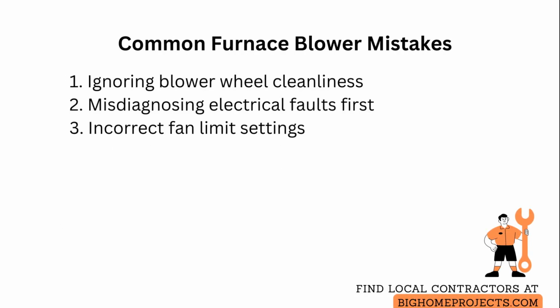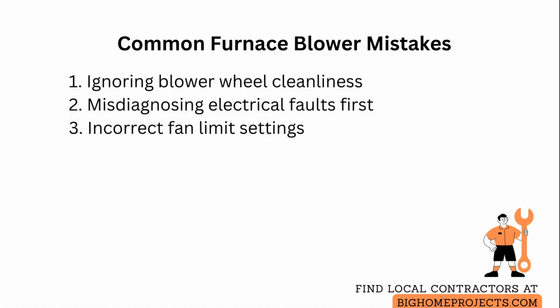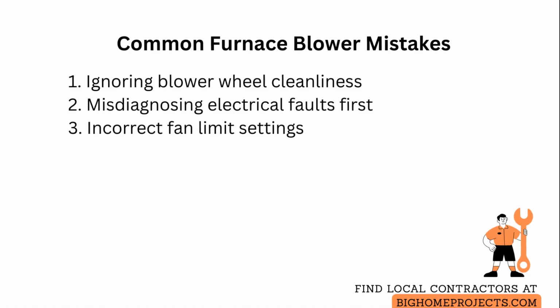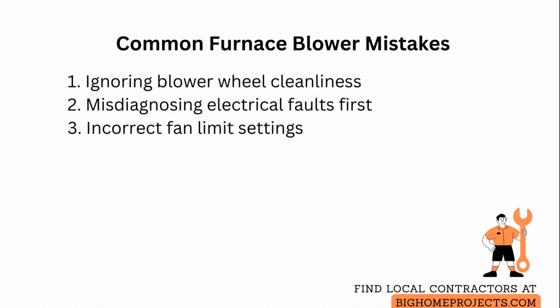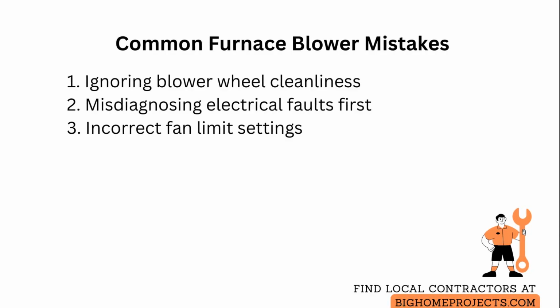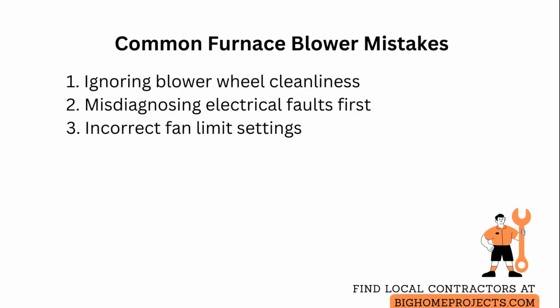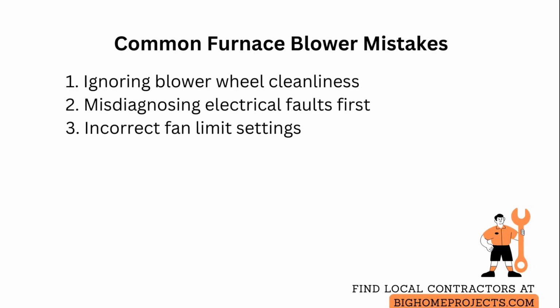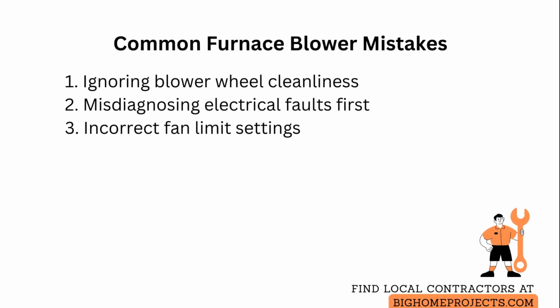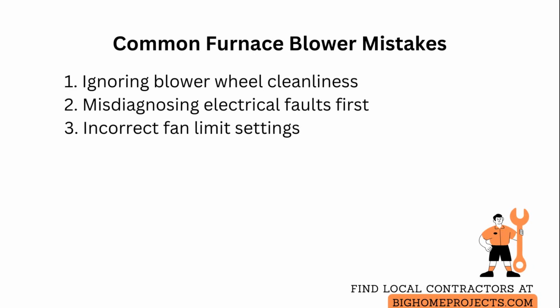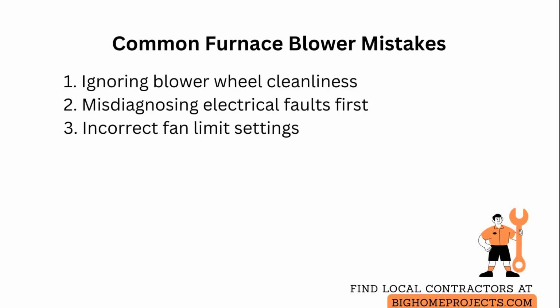Common mistakes include relying solely on filter changes while ignoring the blower wheel, which still causes overrun from imbalance, so clean the wheel and housing when you change filters. Another issue is misdiagnosing electrical faults as control failures. Check wiring and terminals first and use a multimeter to confirm voltages before replacing control boards.